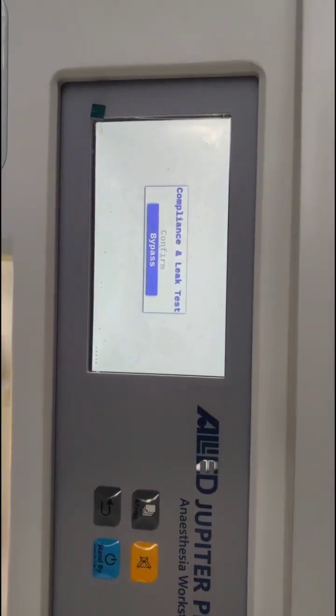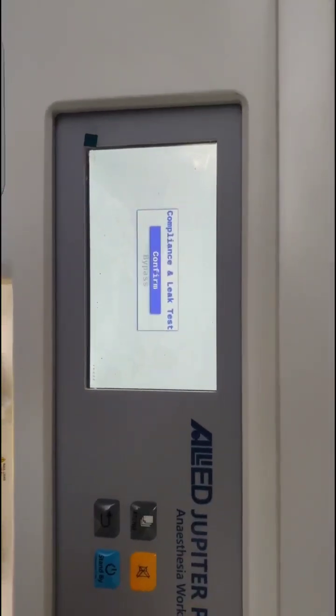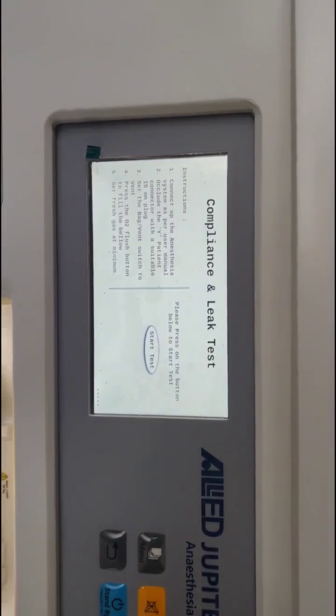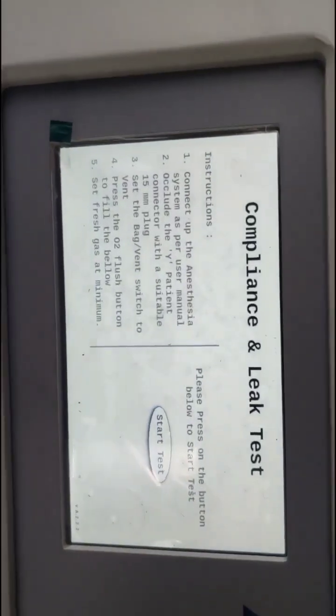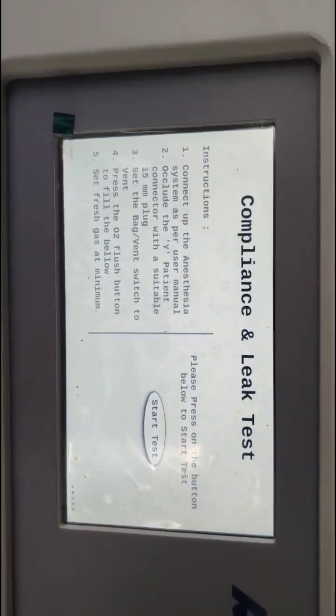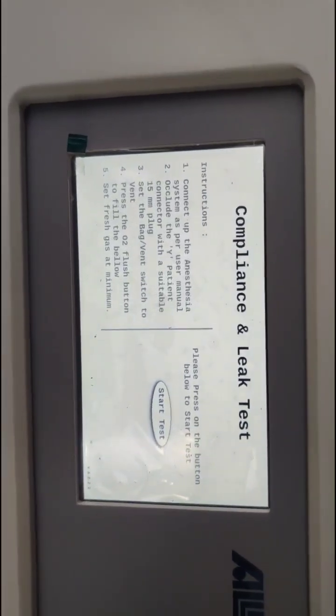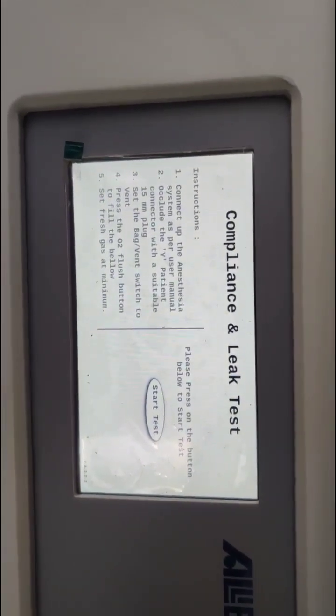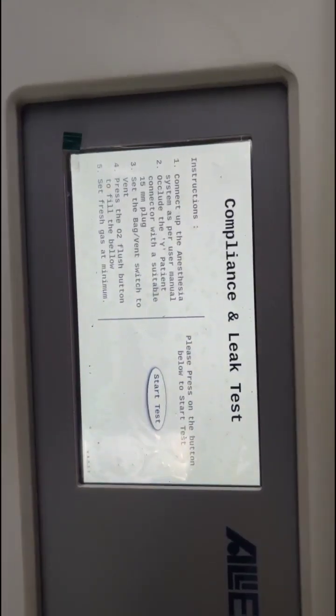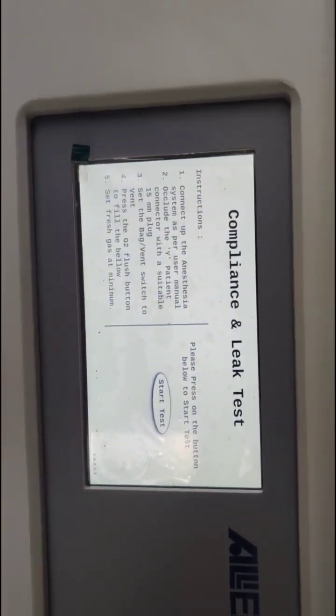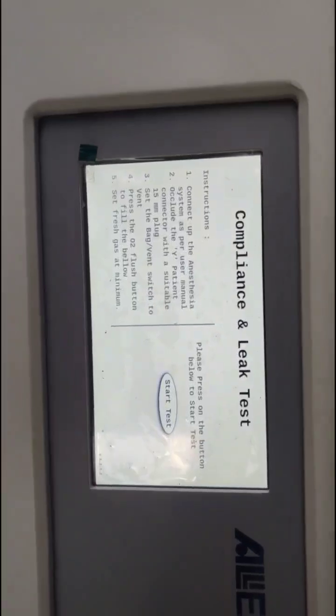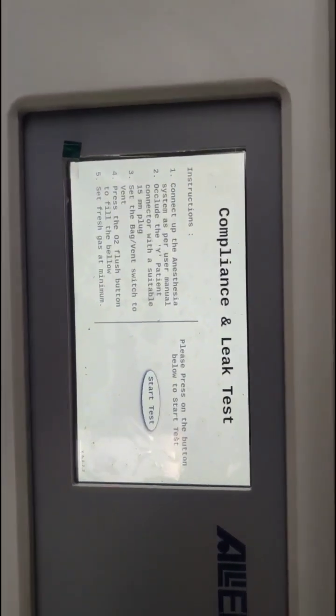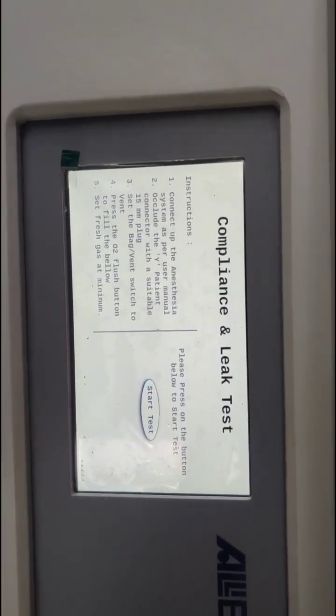So this is the first step, that you have to do the compliance and leak test. For the compliance and leak test, these are the instructions that you have to follow. You have to connect the anesthesia system as per the user manual, and you have to occlude the Y-piece of the patient circuit, and then start the test. Make sure that the bellows are filled properly, fully, and all the flow knobs are in the off position.